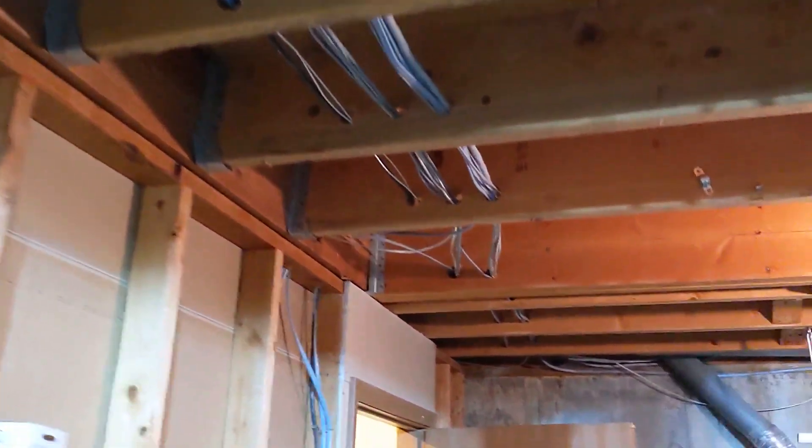The best thing to do is contact an electrician and get a quote. I can give you an example based on our installation. The electrician added a 50 amp circuit in my existing panel, ran the cable up from the basement ceiling over to the garage, punched a hole in, kept the cable in the wall, ran it to where I wanted the outlet, and installed the NEMA 14-50 outlet. It was a relatively straightforward installation — about 40 feet of cable — and the total cost ended up being about $600.